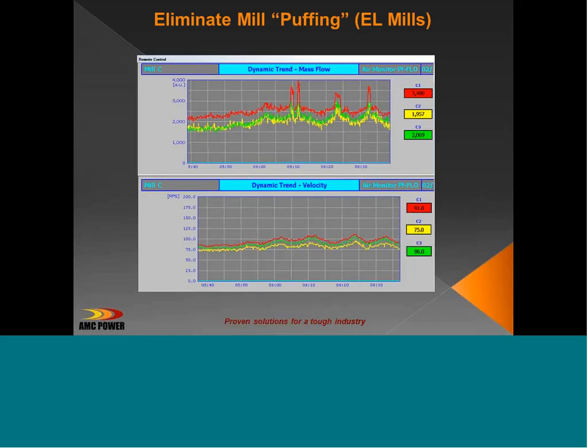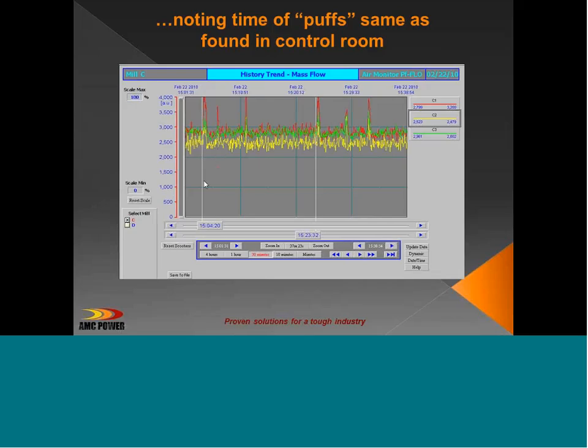Coal flow measurement can also be used for troubleshooting. This is at a power plant that had what they called puffing. Periodically, they would get a high-pressure signal in their pulverizer, followed by a CO spike on the back end of the boiler, in the stack. As soon as we turned on coal flow measurement, we could see that there are times when all 3 pipes from this pulverizer, it's a 3-pipe EL mill, surged. One day we were in the control room, and the operator said, we just had a puff, and we were able to bring our cursor over to the exact instant that they said they had a puff, and we see all 3 pipes spike.